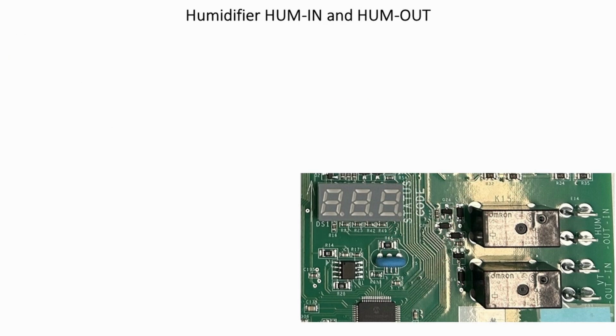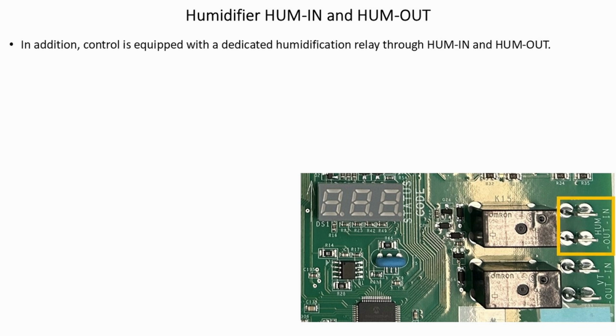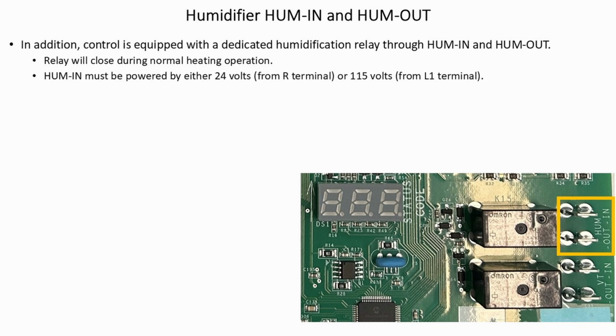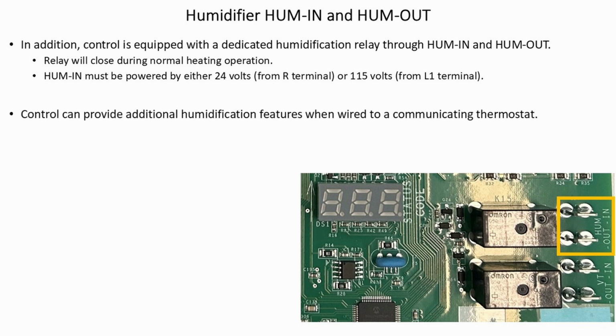Humidifier HUM in and HUM out terminals. In addition, the control is equipped with a dedicated humidification relay through HUM in and HUM out. The relay will close during normal heating operation. The HUM in terminal must be powered by either 24 volts from the R terminal or 115 volts from the L1 terminal. The control can provide additional humidification features when wired to a communicating thermostat.